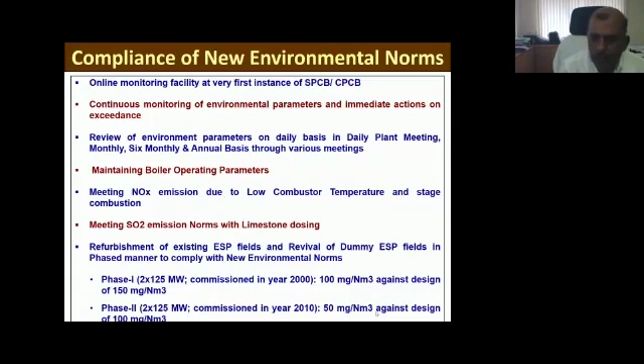But how is the condition now? I would like to present what we discussed. The environmental norms for our phase 1 units, unit 1 and 2, is 100 mg. Against that, we are generally within limit, varying from 70 to 90 normally. This was possible by restoration of all ESP fields, though the dummy field is still left out. We are planning restoration of that dummy field too, so we will always be fully complying with requirements.